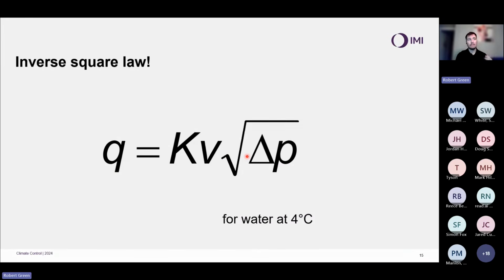And as I said, that is a simplified relationship for water at 4 degrees C, because it is also including the density of water as a factor here, where at 4 degrees C, the density of water is 1000. So that is a brief introduction to the inverse square law and the flow versus differential pressure requirements of a system. It's really important to bear that in mind when we're looking at systems: a small increase in differential pressure is going to give a very small increase in flow, or vice versa. If I wanted a 20% increase in flow, that's not going to be a 20% increase in differential pressure. That's going to be the square of that increase. So it's going to be around, I think, 40%.